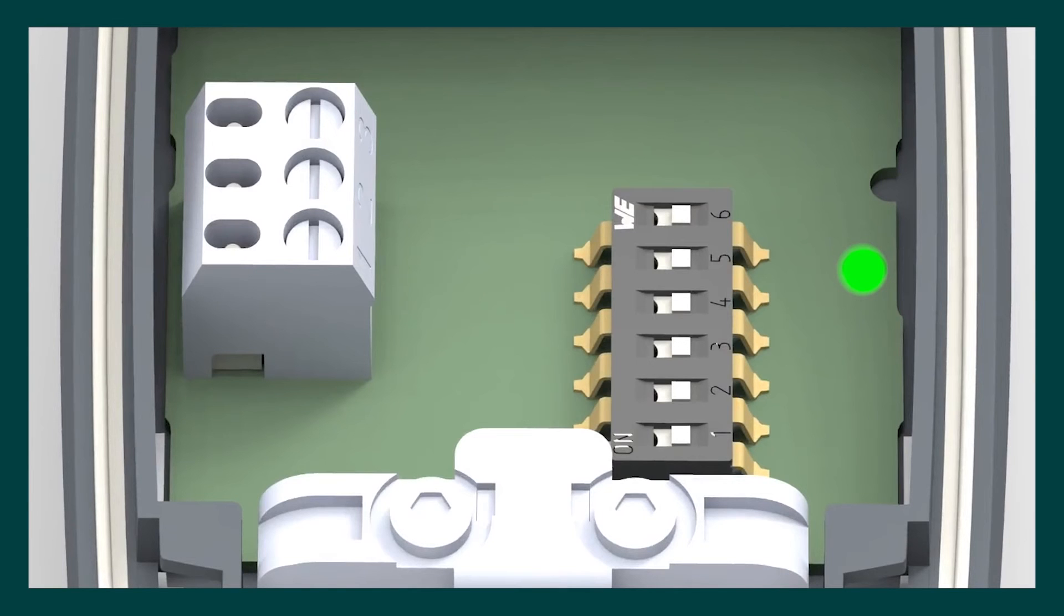To drive the actuator fully open, flip Dipswitch 6 from the off position to the on position, then back to the off position.